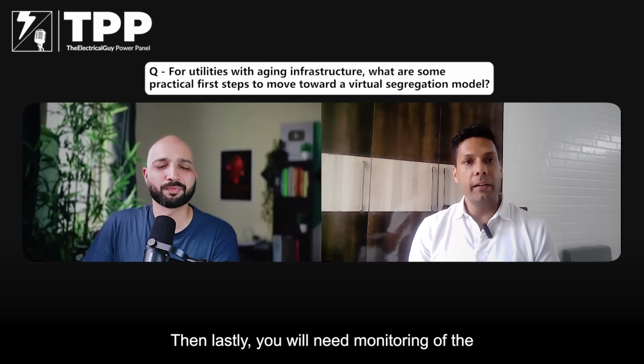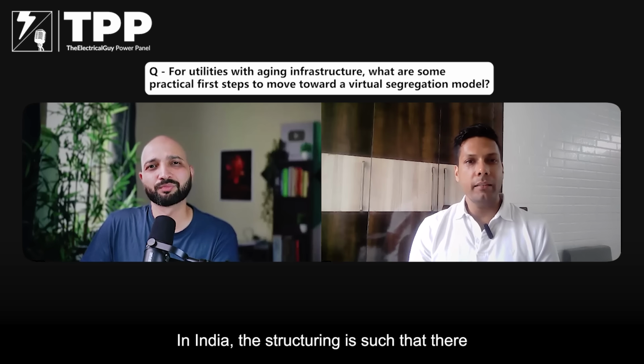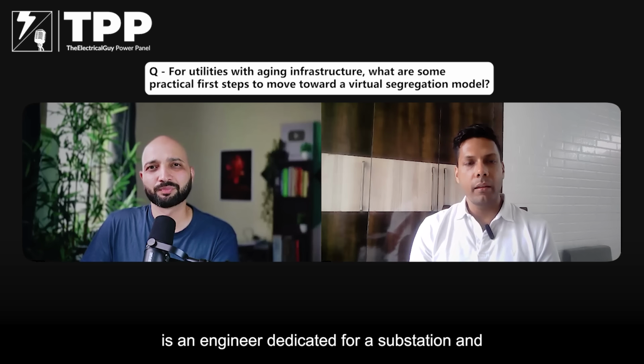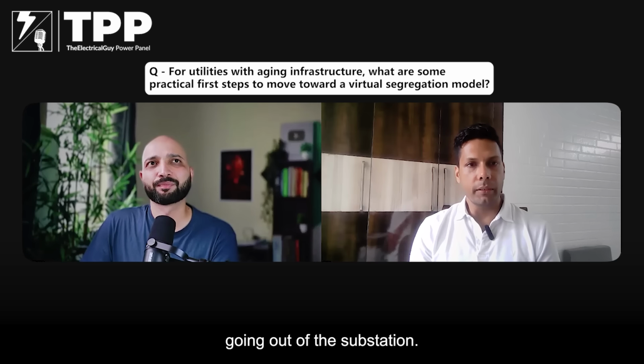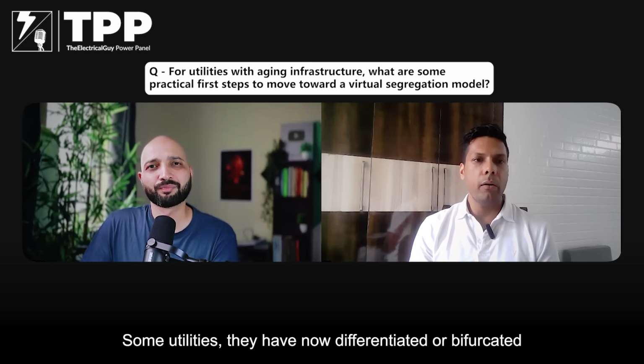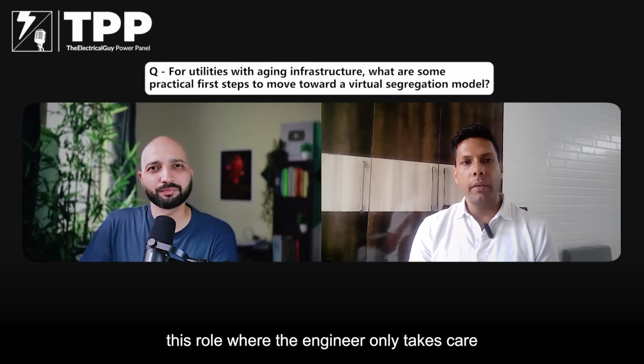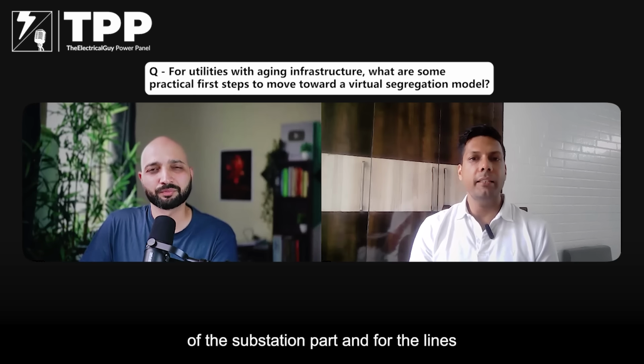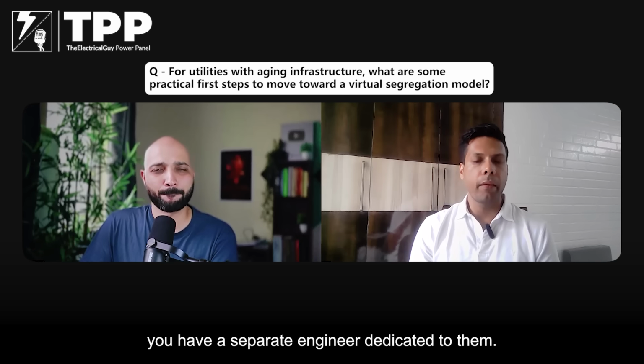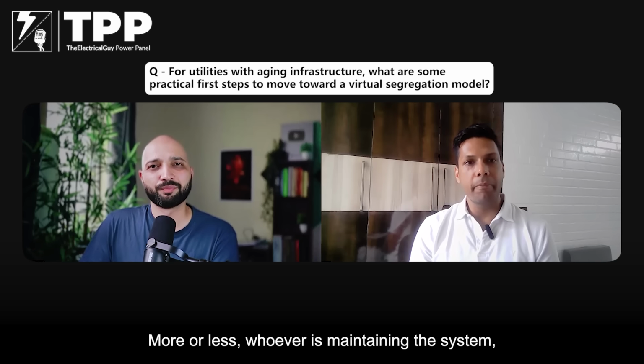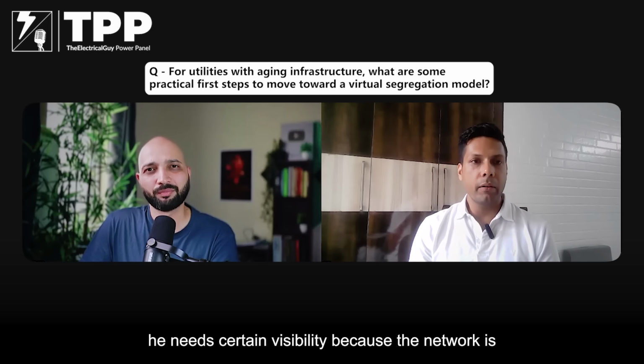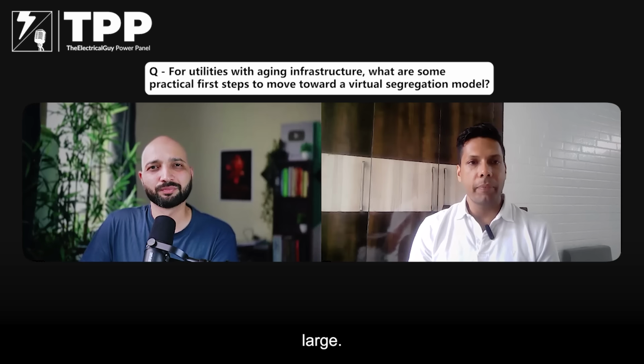Then lastly, you will need monitoring of the network. In India, the structuring is such that there is an engineer dedicated to a substation, and he is taking care of all the networks going out of the substation. Some utilities have now bifurcated this role, where the engineer only takes care of the substation part, and for the lines you have a separate engineer dedicated to that. More or less, whoever is maintaining the system needs certain visibility, because the network is large. Usually there could be 4, 5, 10, 12 feeders also. So you should be aware what is happening in your feeders.